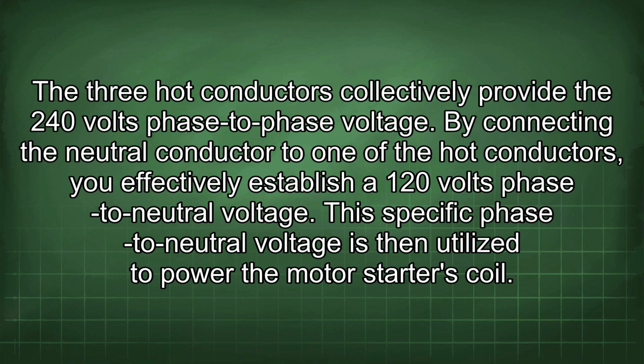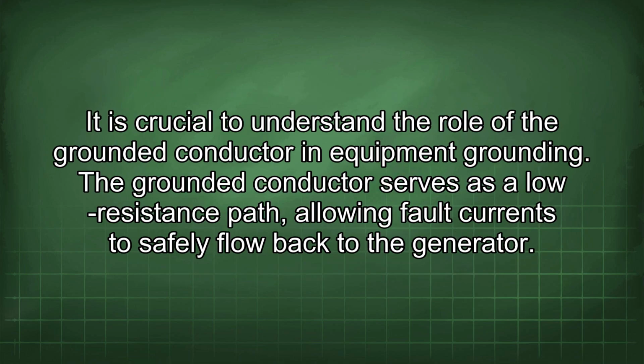The 3 hot conductors collectively provide the 240 volts phase-to-phase voltage. By connecting the neutral conductor to one of the hot conductors, you effectively establish a 120 volts phase-to-neutral voltage. This specific phase-to-neutral voltage is then utilized to power the motor starter's coil. It is crucial to understand the role of the grounded conductor in equipment grounding. The grounded conductor serves as a low resistance path, allowing fault currents to safely flow back to the generator.